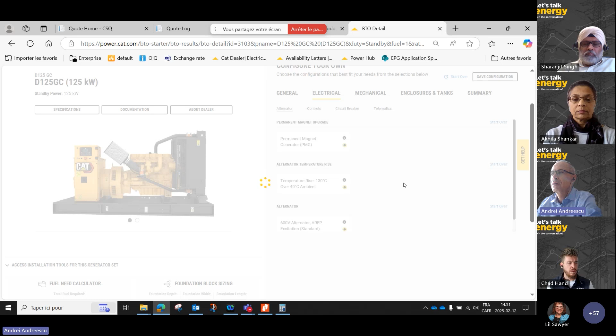We go next and have the choice of several circuit breakers. This generator set can be equipped with 2 of them, and we choose the capacity. For a 125 kilowatt generator set at 600 volt, the main circuit breaker should be 150 amps. If we plan to do yearly testing according to CSA 282, it's probably wise to select a second circuit breaker where the load bank will be connected, also 150 amps. We click next.